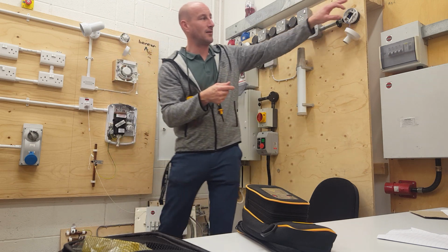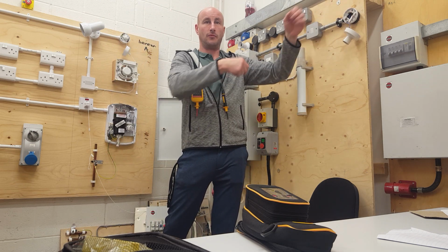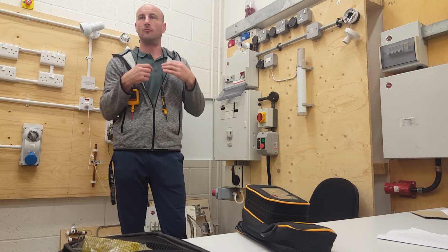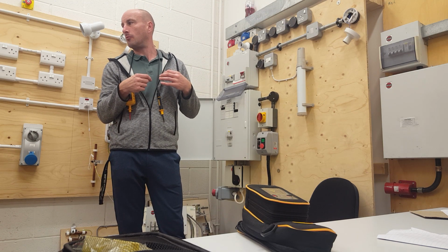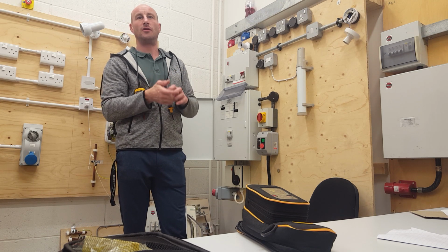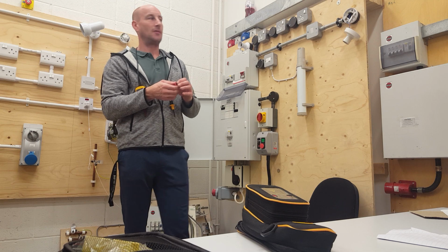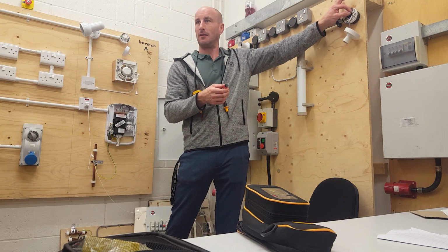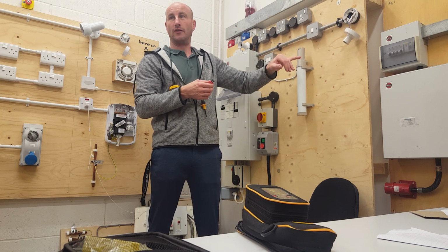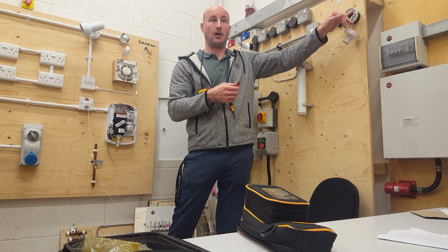So we've done our 3 tests, live, neutral and earth, the different combinations. Is there anything else we should do before we can test the tester and move on? Check the switch. It might be turned off at the switch. This is a switch line, there's no feed, it's a switch wire. So potentially, if I turn that on, it could give power to the light, can't it?